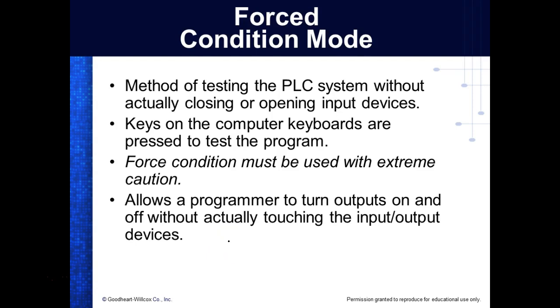Force. Everybody okay on forcing? This PLC is really easy. It's real easy. With Siemens, you have to set up a force table. So you have to go in and say, I want to force this contact, I want to force that contact, and you have to enter everything you want to force. For Allen Bradley, you just go to that force table, and all you have to do is make sure you know the address, right?